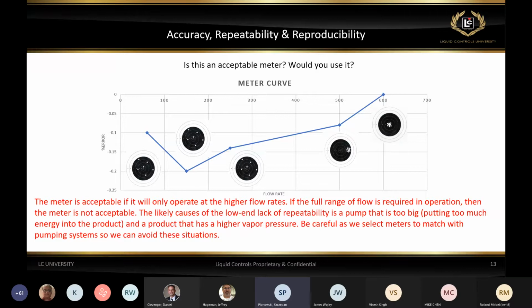Most likely not. When you see a curve like this, when it starts with very repeatable points and then goes into points that may be accurate but not, or seem to be accurate but not repeatable, that's really an indication of a system issue. In most cases, you're dealing with a pump system that is way too much for this meter. So we're generating too much energy from the pump that has no place to go. You get to the point that you start chopping up the product, start putting entrained air into the liquid because of all the energy the pump is generating. And you go from a meter that is accurate and repeatable to a meter that's not repeatable at the lower flow rates. That happens more in a situation where you're measuring a liquid like LPG with a little bit high vapor pressure.